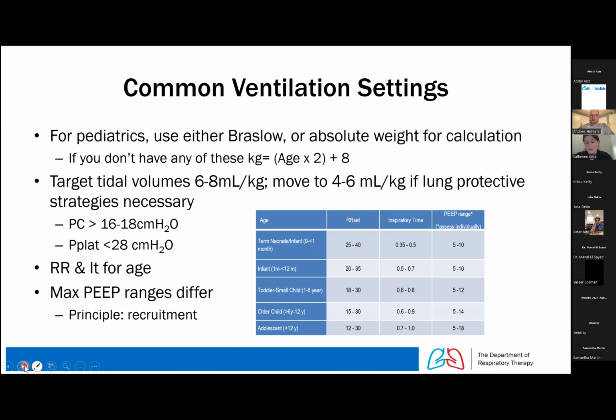Your pressure control typically shouldn't be much above 16 or 18, and we're looking for a P-plat less than 28. The two settings that get adjusted for size or age are your respiratory rate and your I time. I've put a little chart here with some broad ranges, where your RTs can help you assess whether they're set appropriately.